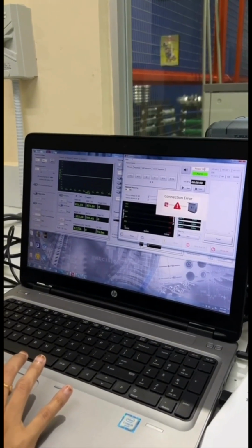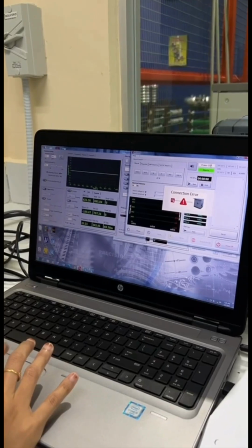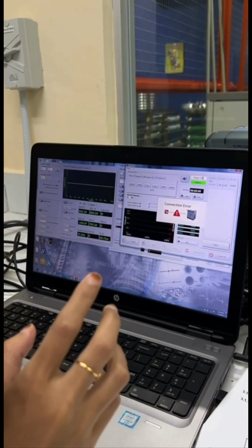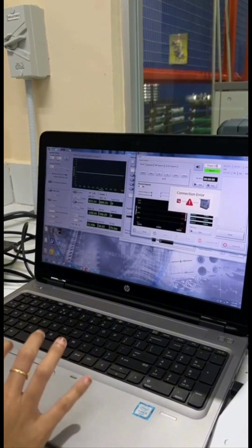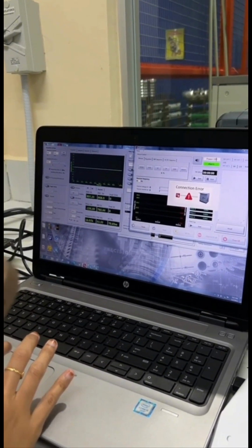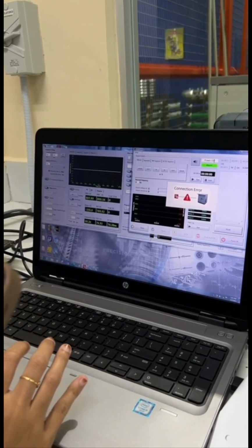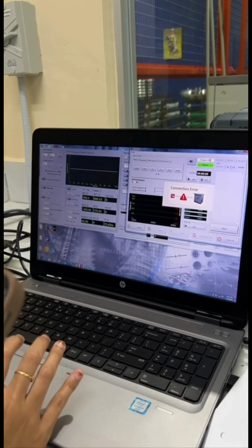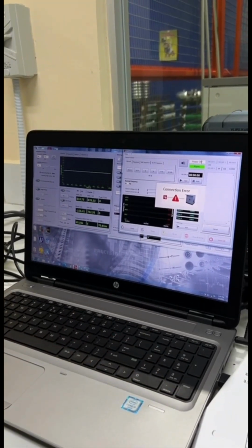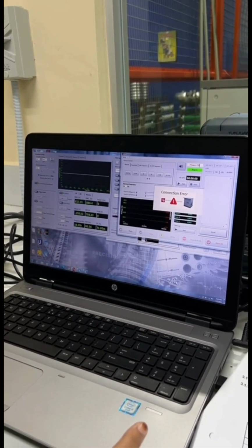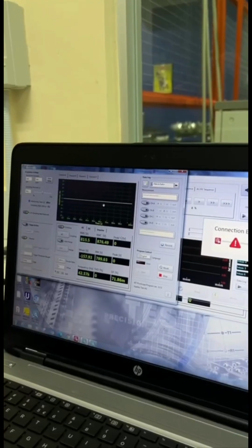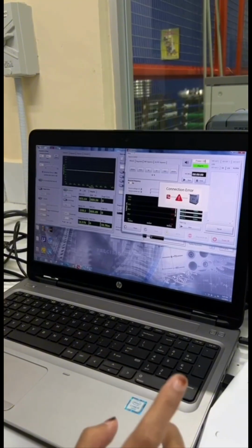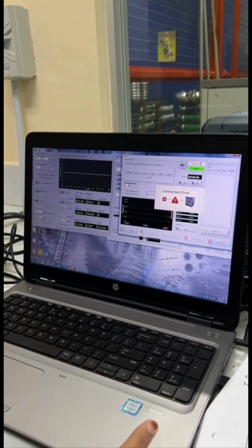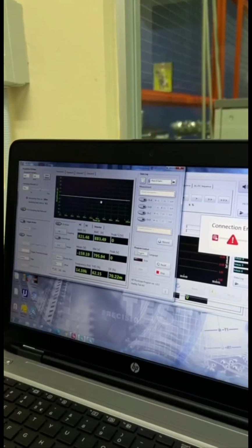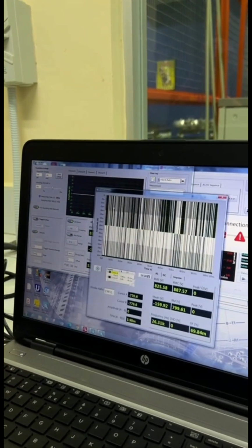So at the start of the operation, there is a 7-second interval. During this time, the earthing, grounding switching rod will move away from the top electrode of the transformer capacitor. If no further action is taken within these 7 seconds, the earthing rod will automatically return to contact the top electrode. This will safely discharge all the voltage stored in the high voltage transformer. So, subsequently, the display interface is activated to observe and analyze the waveform generated during the injection process.